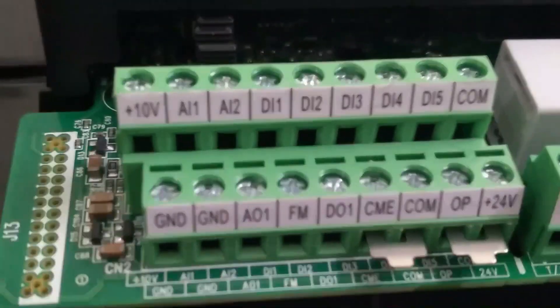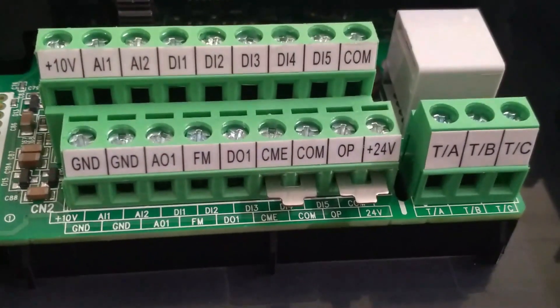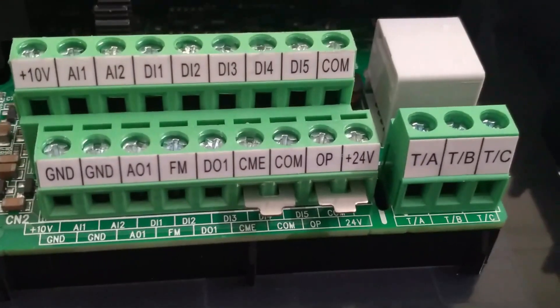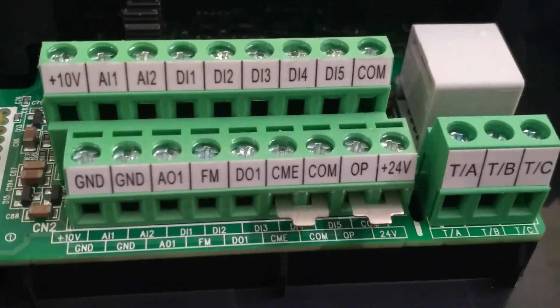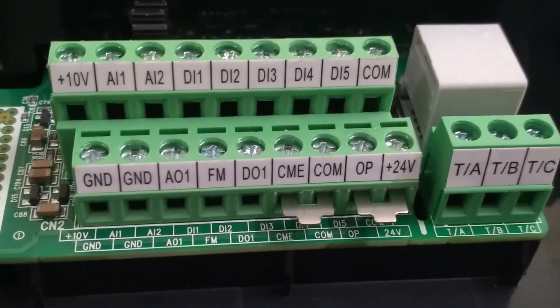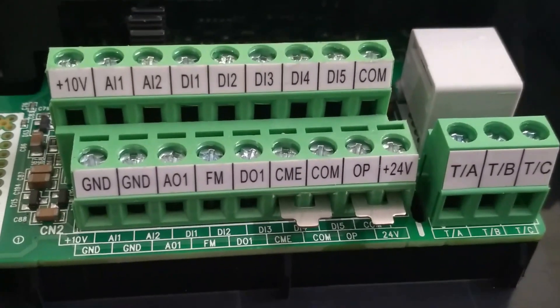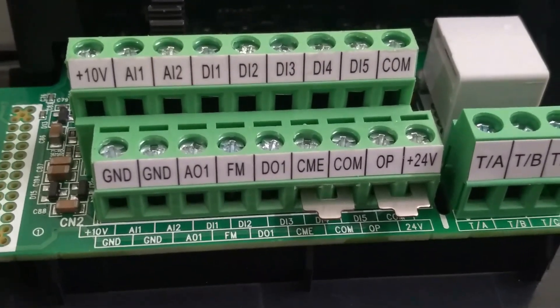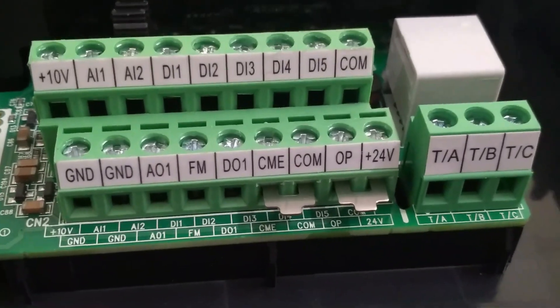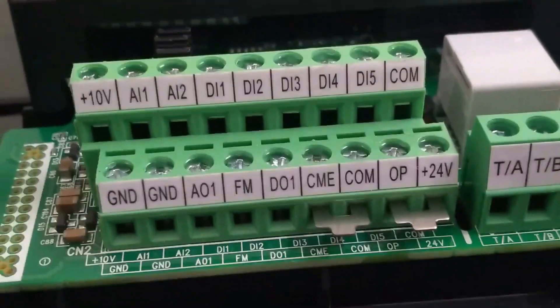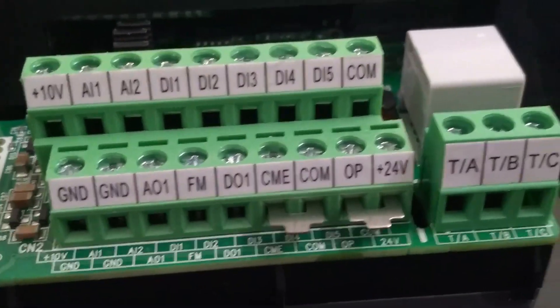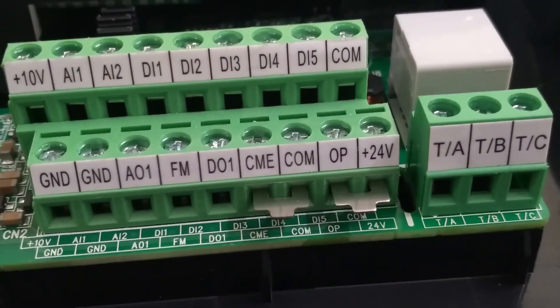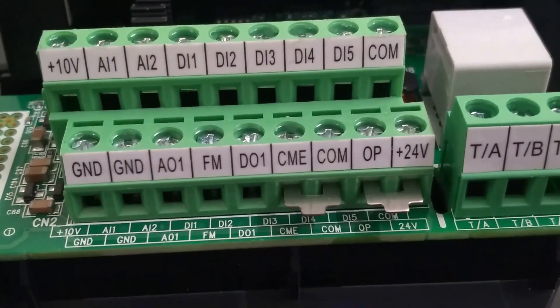First we have DC power supply terminals, which are +10 volt located at the top left. Next is +24 volt which is located at right bottom side. OP terminal is shorted with +24 volt terminal. These are all power supply terminals. +10 volt is used when potentiometer is connected to VFD for speed control. +24 volt is used for connecting digital inputs. If external DC 24 volt supply is used, we have to remove the shorting of OP terminal and connect the +24 volt to OP terminal.